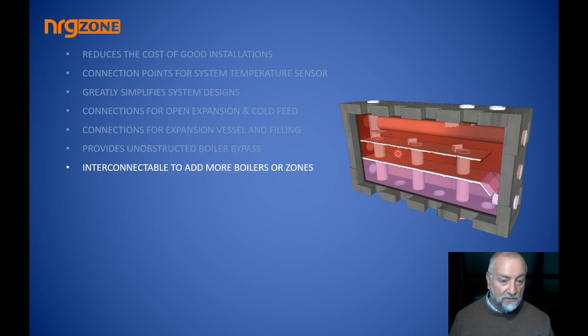So you've seen multiple examples where you can have a manifold collect heat or heat sources and deliver to other manifolds. We've got one job where we have one major boiler house delivering with a major manifold with 7 zones, each of them going to 7 independent buildings. Each building has its own manifold, and some of them have their own heat sources on the other side of the manifold. So it just means that we can make an extremely complex job very, very simple.